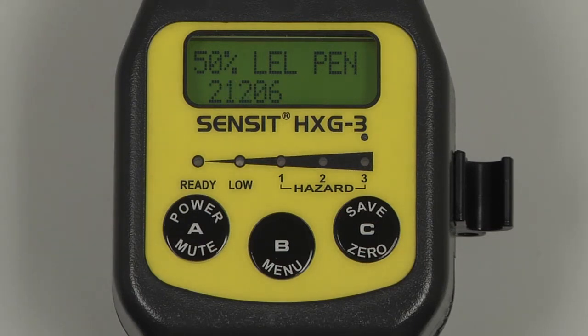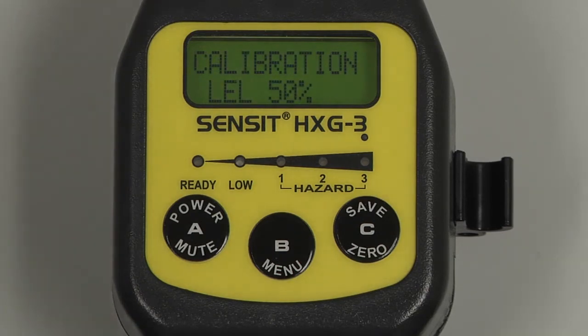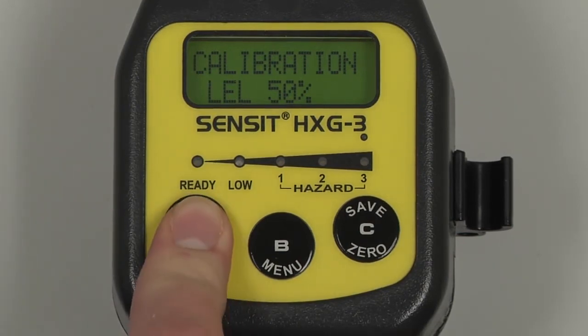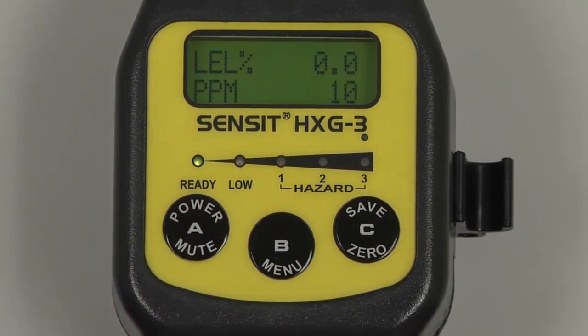Once the instrument has achieved a stable reading, data saved will be displayed, and the calibration will be complete. The data was saved and the calibration is complete. You can remove the cal adapter from the inlet at the end of the gooseneck, turn off our regulator. You can now exit back to the user menu and to the working display by pressing and releasing the A button, and allow the instrument to clear before powering off.